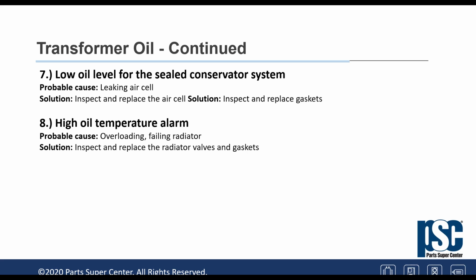But again, the heat doesn't care. I mean, if the oil goes up, it's because the winding also went up from overloading. Also, again, poor cooling circulation will create the problem. And again, replace the radiator valve and gasket if indeed that's the cause of it.